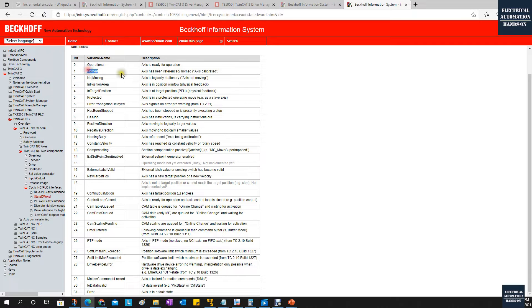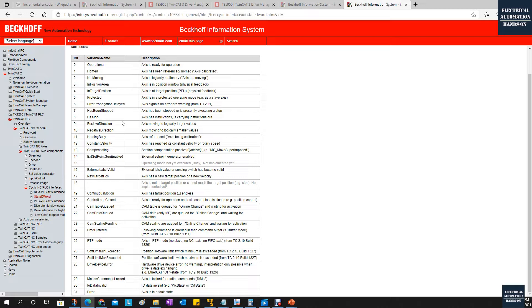Another important bit is HOMED — if you are doing positioning control, the machine needs to home the axis, so this bit is very important. MOVING represents whether the axis is at standstill or moving. Bits 9 and 10 represent positive direction and negative direction — which direction it is moving. Bit 7 'HasBeenStopped' turns on after you command the axis to stop. Also important are 'DriveDeviceError' at bit 28 — if your drive has something wrong this bit turns on — and bit 31 'AxisError' — if your axis has something wrong, maybe a hardware error or configuration issue, this error bit will turn on.